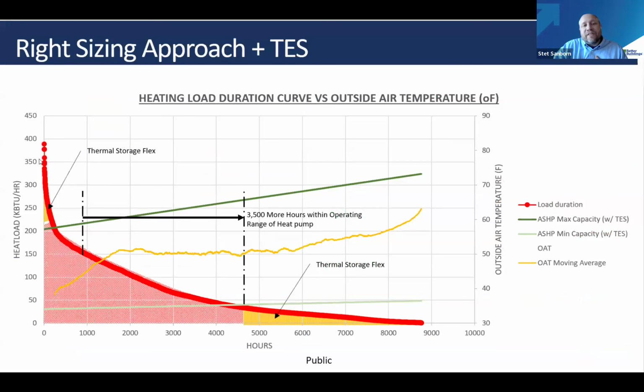But I did want to share, this is a different way of looking at that same chart that I showed from the Center for the Built Environment. If we take all the heating hours of our year and we stack them from highest to lowest, you can see, again, even our own modeling shows that we have very few hours at that peak load and a lot of hours at very shallow load, very small load. Heat pumps don't like to operate in either of those regions. And so thermal storage allows us to meet the peak with a small heat pump, but even better, it allows us to meet what we call part load conditions with the thermal storage, and then let the heat pump just turn on periodically to recharge the tank. And so we're not asking the heat pump to keep turning off and on really fast or try to hunt for a low load.